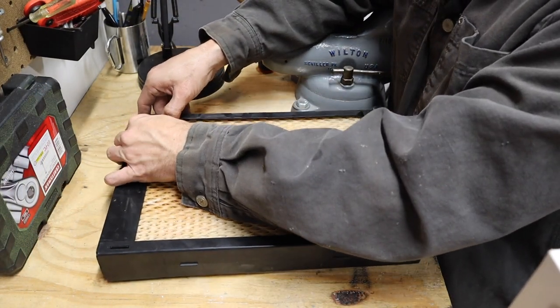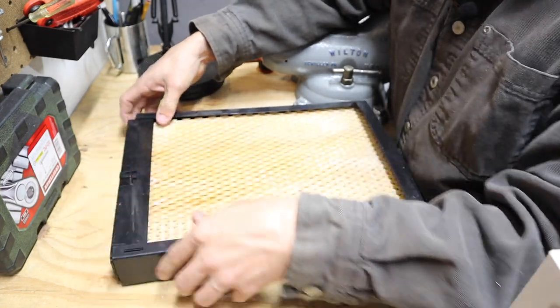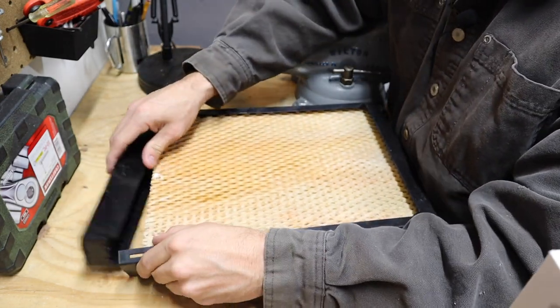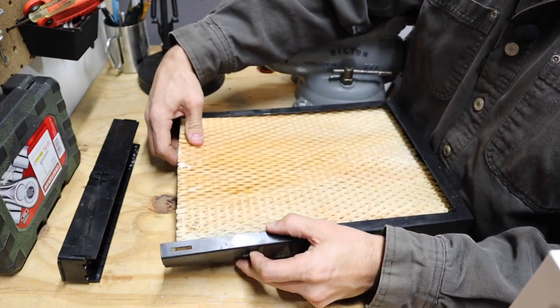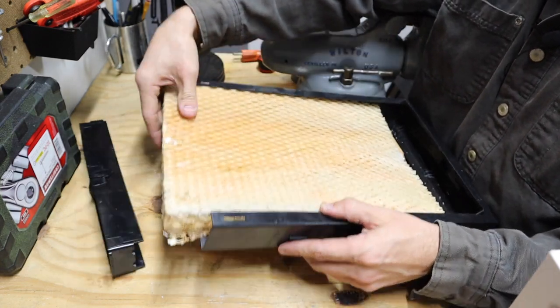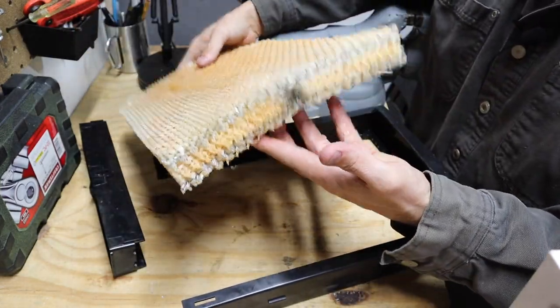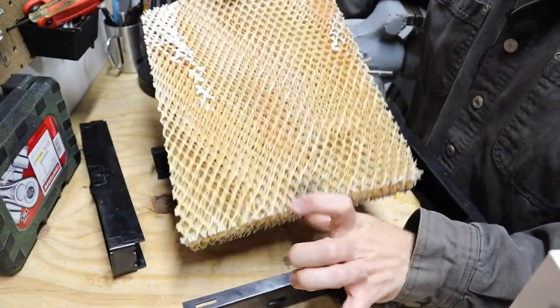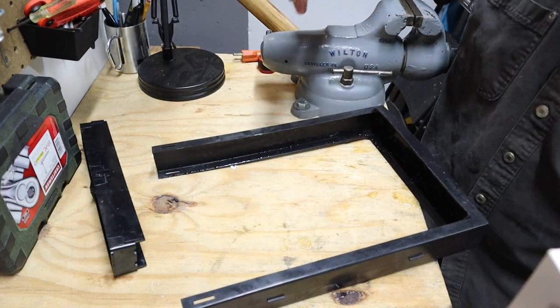So if you are going to your big box store or shopping for your media here, the way to do this is simply just measure the dimensions of this media. So this is a 10 by 13 filter and you can see it's just literally saturated with water. This goes in the trash. It's pretty nasty.